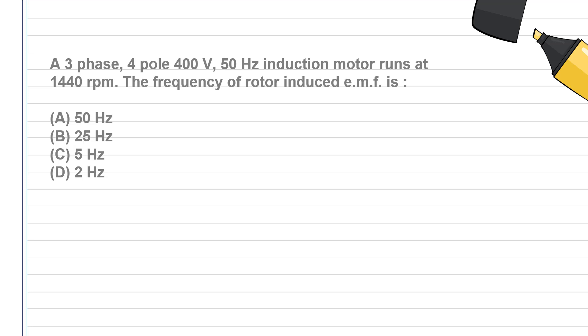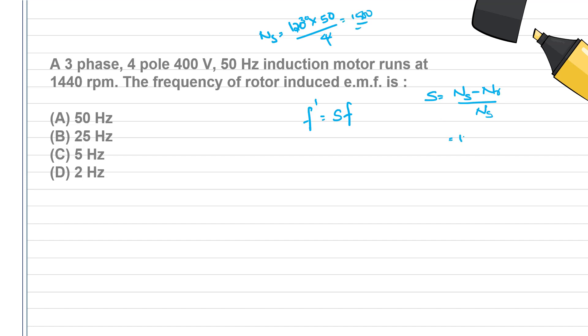The frequency of the rotor-induced EMF is f' = s × f, where s is the slip and f is the supply frequency. Slip s = (Ns − Nr) / Ns. Ns = 1500 RPM, Nr = 1440 RPM. So s = (1500 − 1440) / 1500 = 60 / 1500 = 0.04. Therefore rotor frequency f' = s × f.